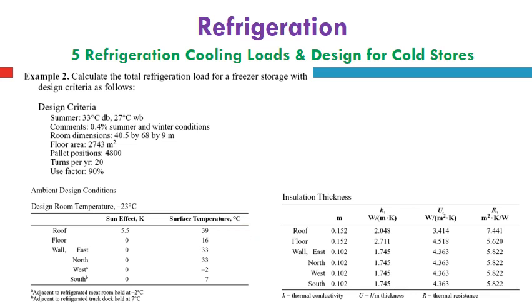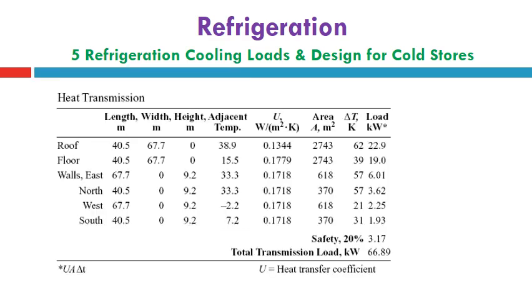The insulation thickness is also listed here in this table for different roof, floor and wall materials, by listing the different Ks, and then getting the overall heat transfer coefficient factors, and finally its inverse, the thermal resistance in meter square Kelvin per watt, are also listed here in this table to help you. Then the heat transmission for each value can be concluded inside this table by taking a safety factor of 20%.